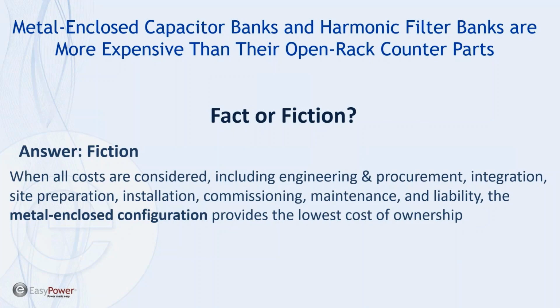Another question that often comes up is when we're being compared against open rack harmonic filter banks. It's often said that open rack filter banks are less expensive and metal-enclosed systems are more expensive. We also say that this is fiction. When all costs are considered, including engineering and procurement, integration, site preparation, installation, commissioning, maintenance, and liability, the metal-enclosed configuration provides lower cost of ownership.